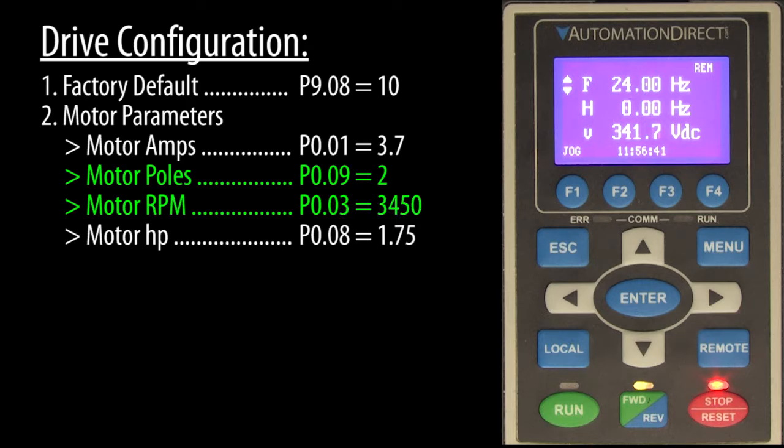I love that the GS4 is smart like that and it won't let me screw it up, but if you don't know to look for the poles parameter, you might wonder why you can't change the RPM above 1800. So set the poles parameter first if you're using a high speed motor.